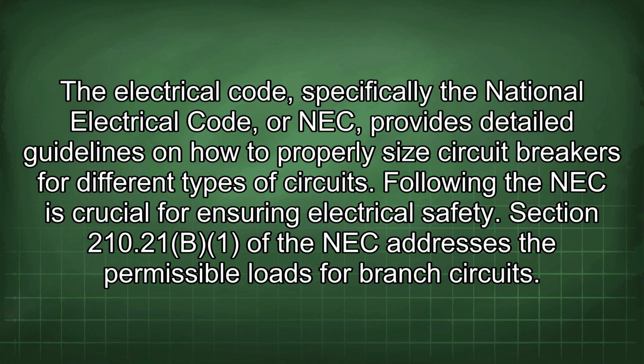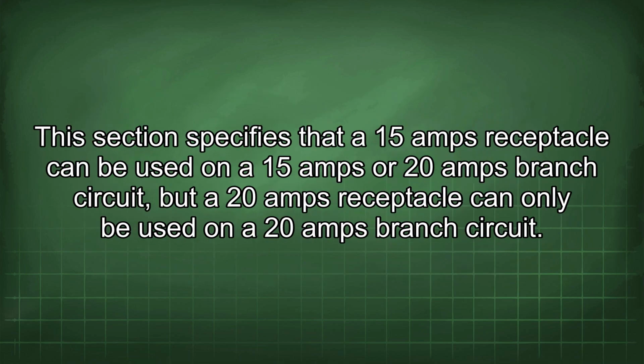Section 210.21 of the NEC addresses the permissible loads for branch circuits. This section specifies that a 15 amps receptacle can be used on a 15 amps or 20 amps branch circuit, but a 20 amps receptacle can only be used on a 20 amps branch circuit.